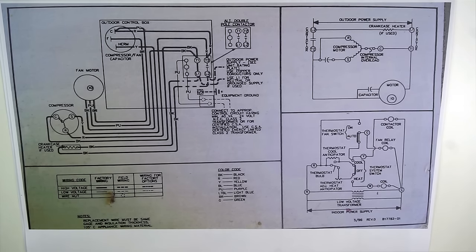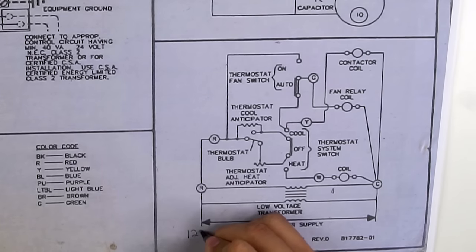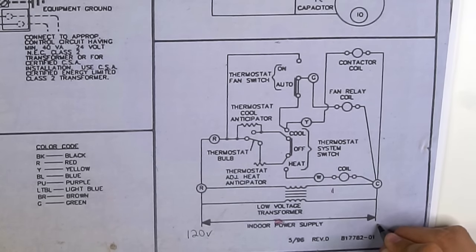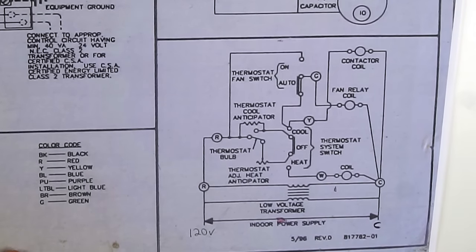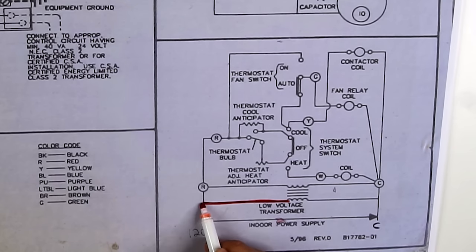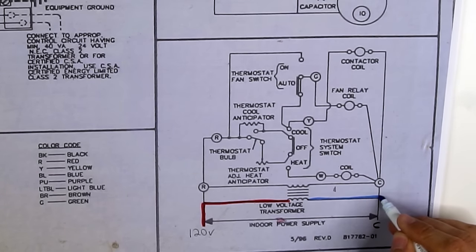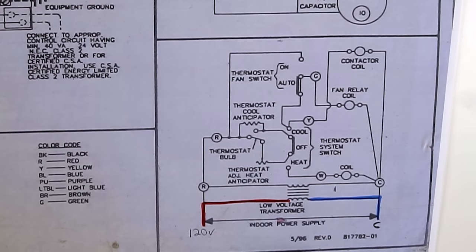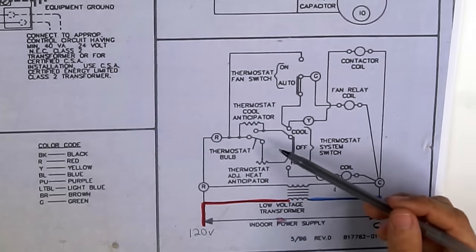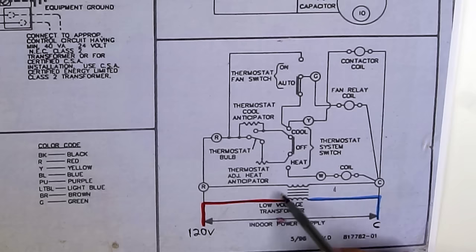Right here it says we have the indoor power supply — this is in the furnace or air handler, and in most cases it's going to be 120 volts. You'll have 120 volts hot coming in on one side and your common on the other side. The transformer symbol — three lines with windings on either side — is a step-down transformer. It gets 120 volts and steps it down to 24 volts. So the furnace gets 120 volts, the power reaches the transformer, and the transformer steps it down to 24 volts.